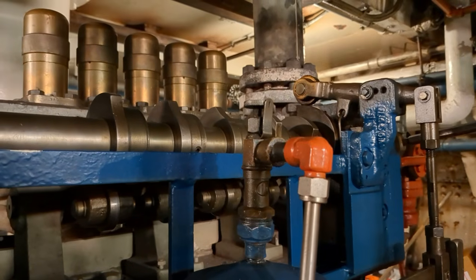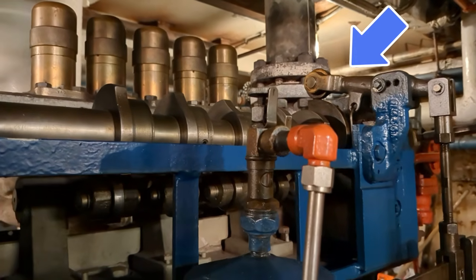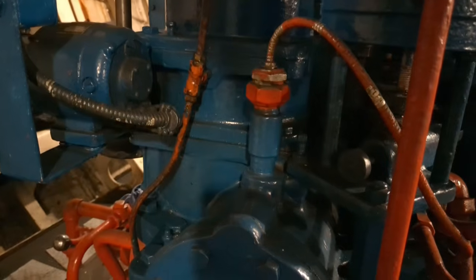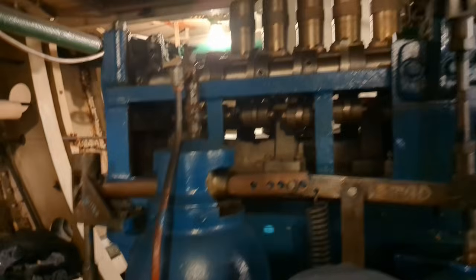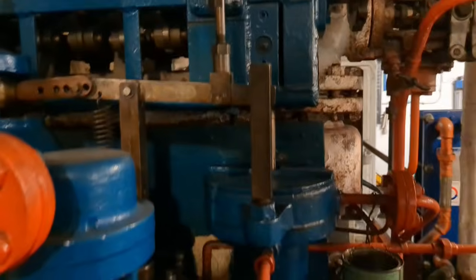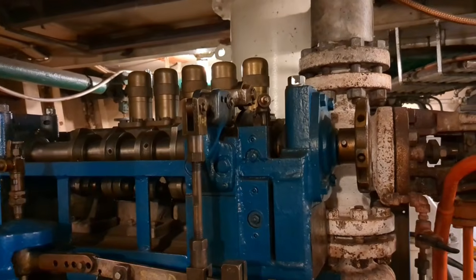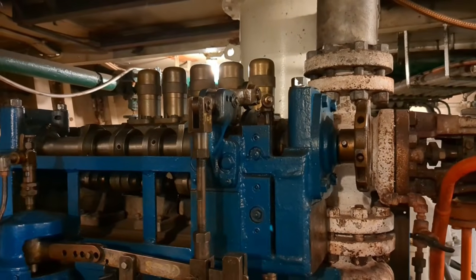One of the cams also operates a compensation mechanism that works against the governor. This introduces a small amount of speed droop, allowing generator load to be shared properly when multiple generators are operating together.